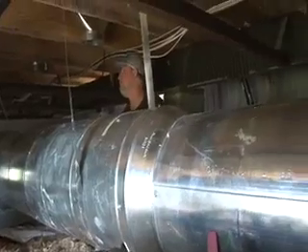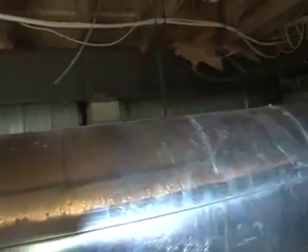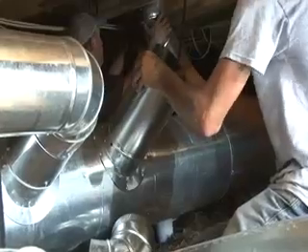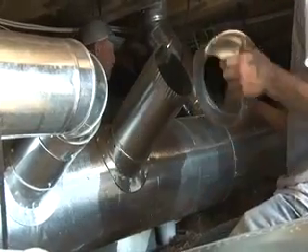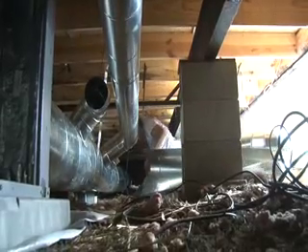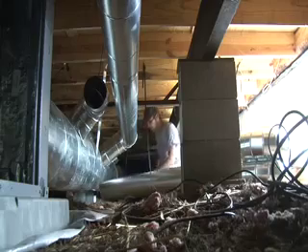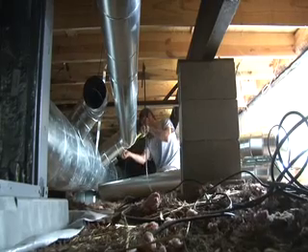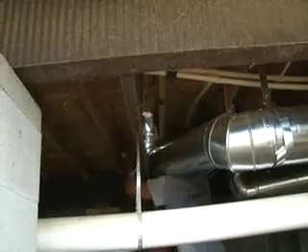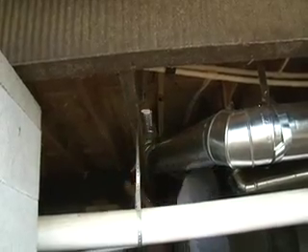We also discovered the existing duct system was too small for the air handler, or the device that forces the conditioned air through the ductwork. This scenario created a very noisy environment anytime the unit was running. Plus, much of the old fiberglass insulation was not making contact with the ducts, causing unwanted condensation under the home. The solution was a properly sized, rigid duct system.